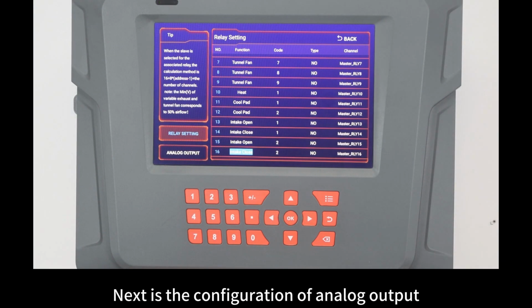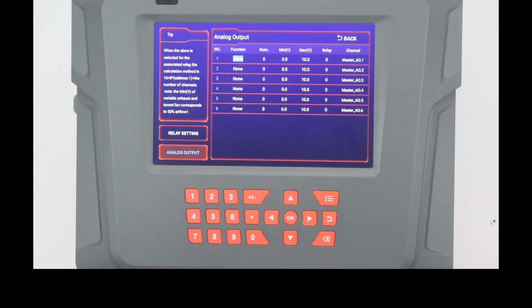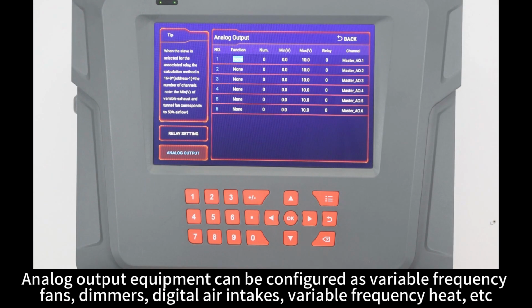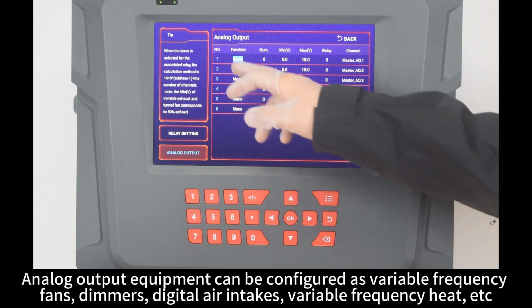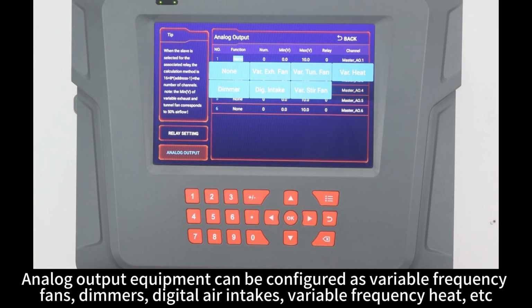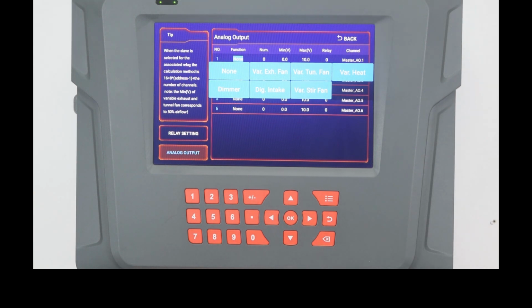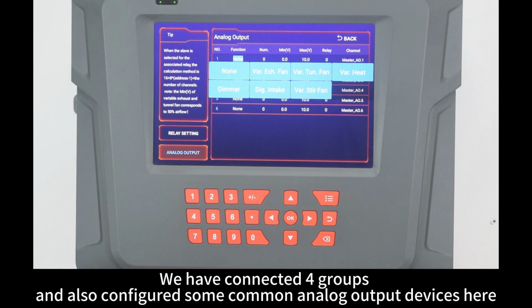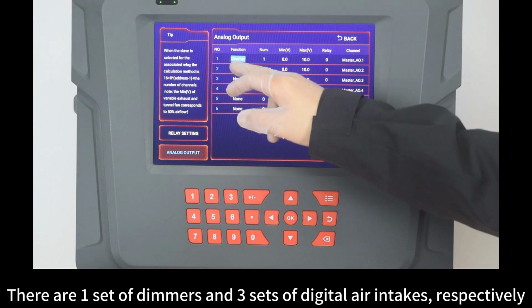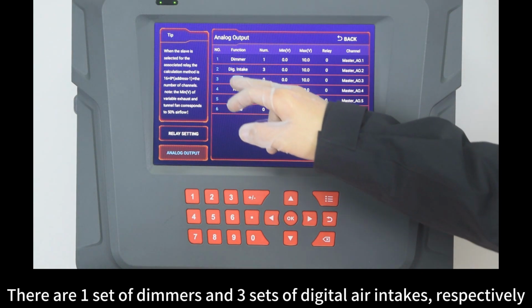Next is the configuration of analog output. Analog output equipment can be configured as variable frequency fans, dimmers, digital air intakes, variable frequency heat, etc. We have connected four groups and also configured some common analog output devices here. There are 1 set of dimmers and 3 sets of digital air intakes, respectively.